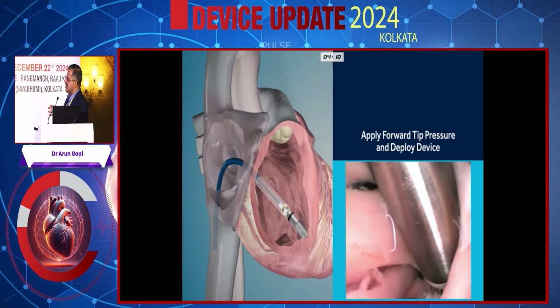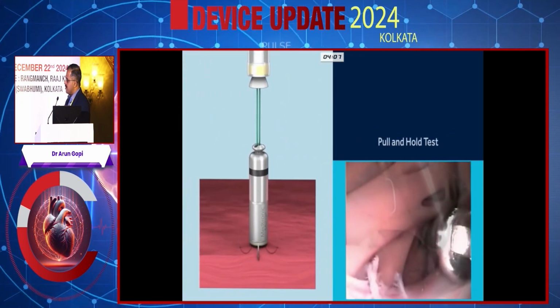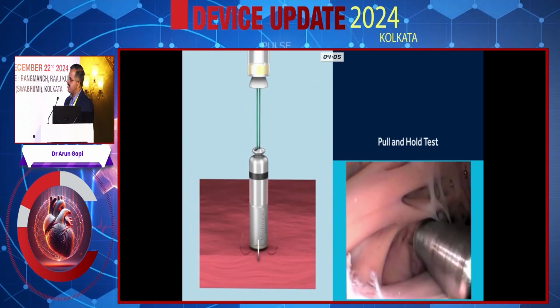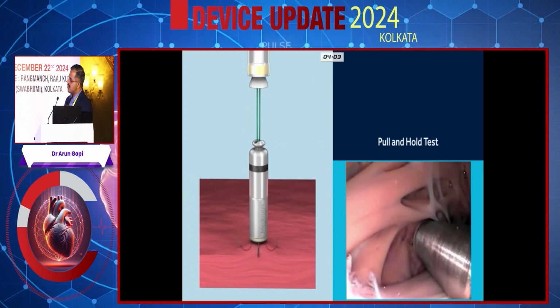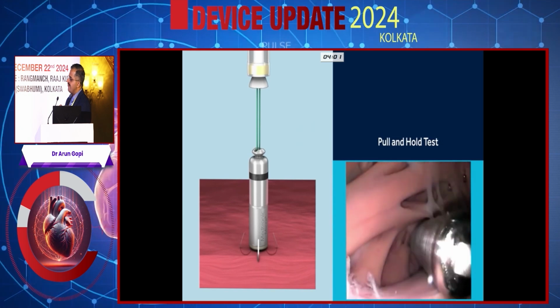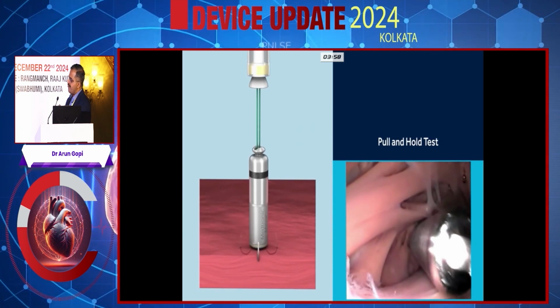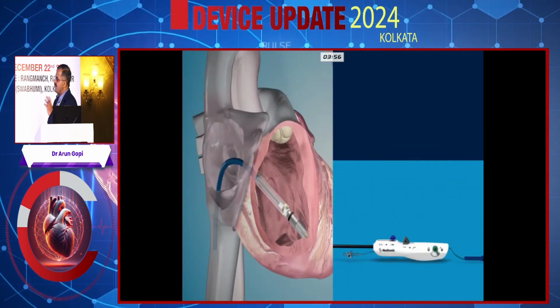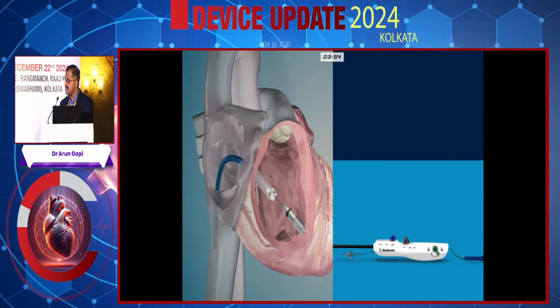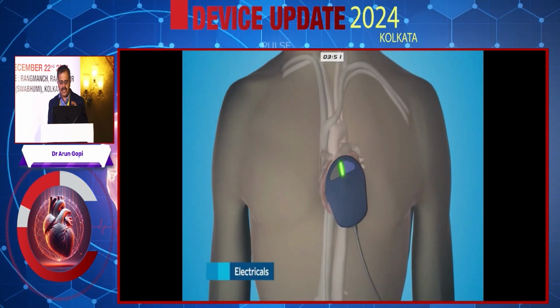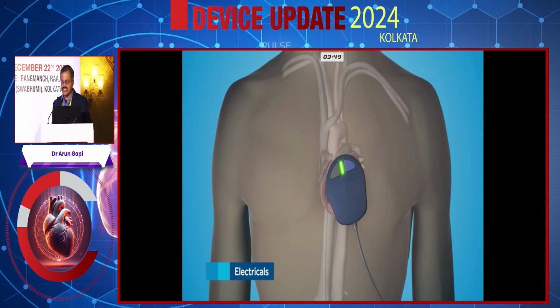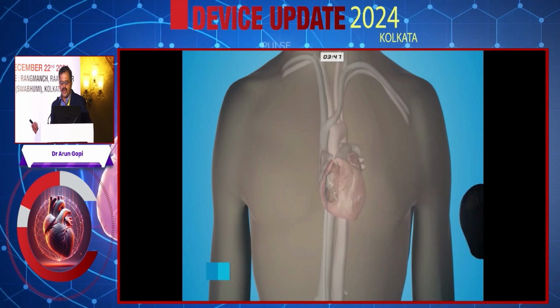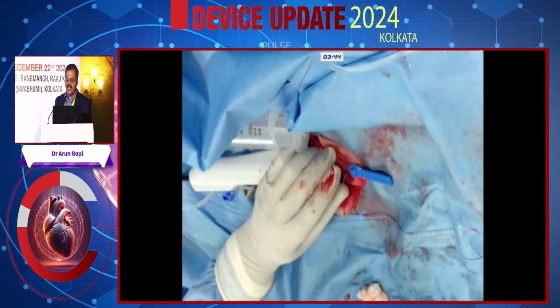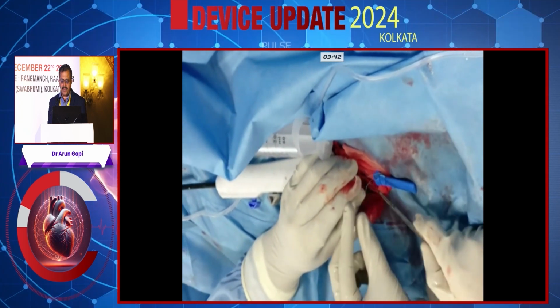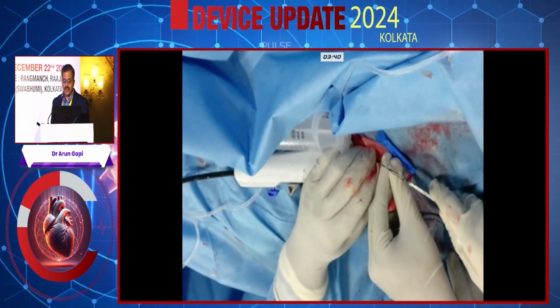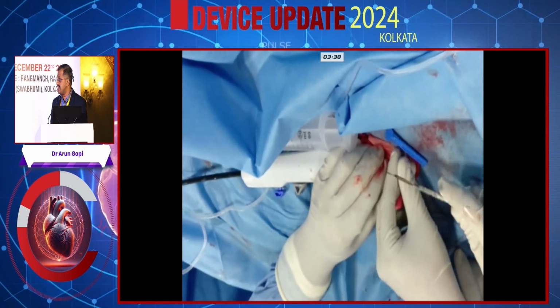This has a very novel fixation mechanism compared to the leads we have, which is called the flexible nitinol tines. Each of the tines has 8 times the holding force keeping the device in position. So even if 2 tines are fitted in, it has 15 times the holding force for the device to stay in. That is what ensures excellent stability. That's where you find 0% dislodgement rates, and you can wirelessly interrogate this device with wireless telemetry. You can check whether the electrical parameters are good, and once they are good, with the cut of the tether, this device is released into the heart, and then it stays in there.